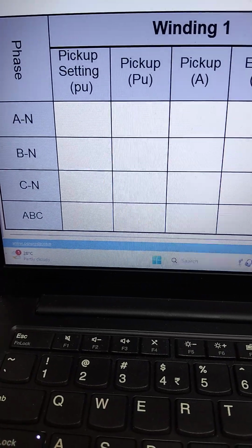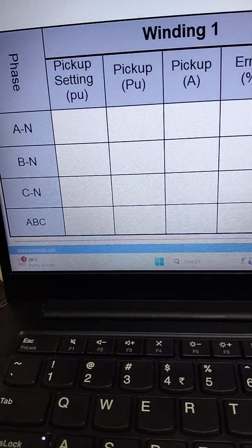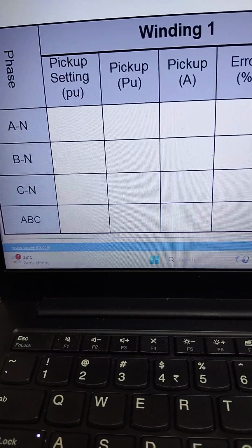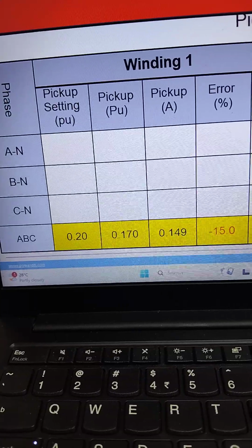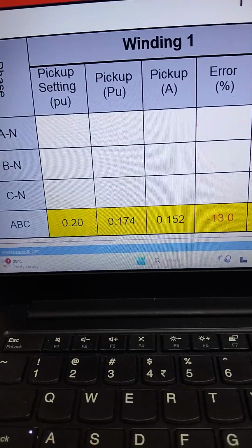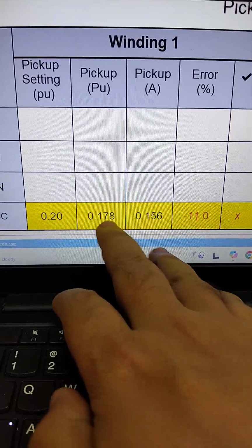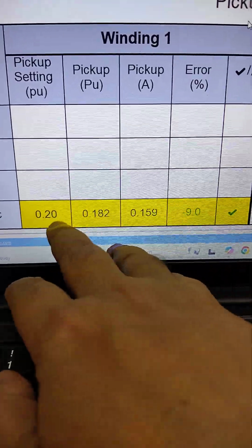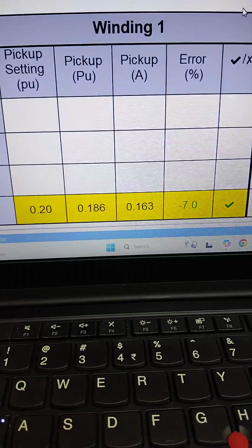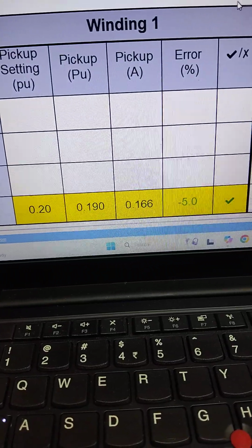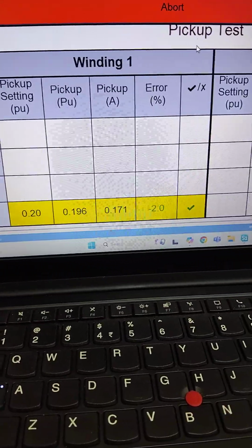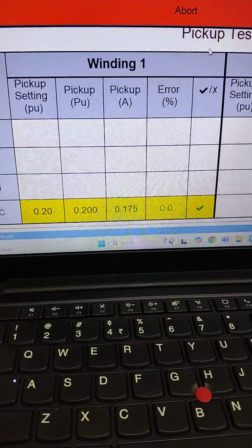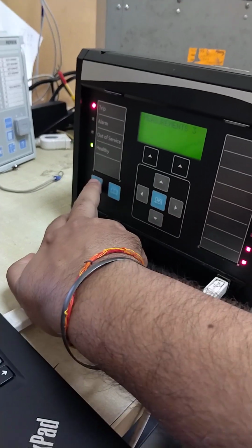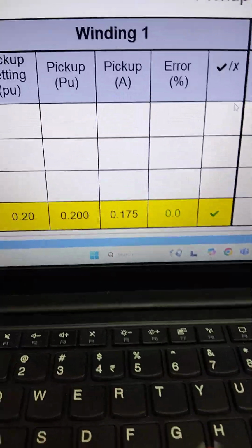In this the kit slowly injects some current, and it expects some pickup value, meaning the 20% value. So once the device reaches that 20% value, 0.2 is the 20% value. So the kit will inject the current slowly and it will increase the differential current, and as soon as it reaches 0.2, it will expect some tripping. So it took place exactly at 0.2. So this is a pass indication, so that's why we're getting a green check.